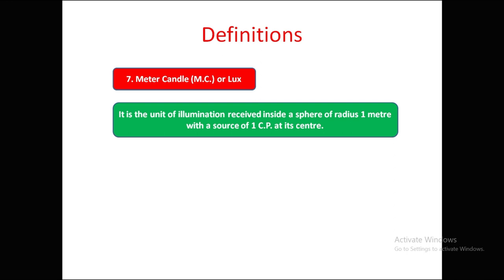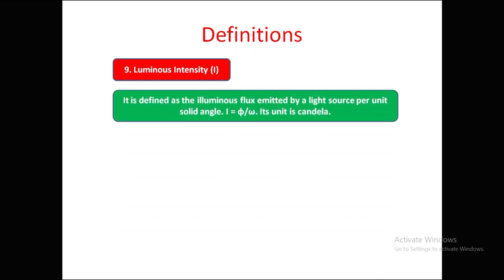Meter candle or lux is the unit of illumination received inside a sphere of radius one meter with a source of one candle power at its center. Foot candle uses the same definition but radius is measured in feet. One foot candle equals 10.76 lux or meter candles.